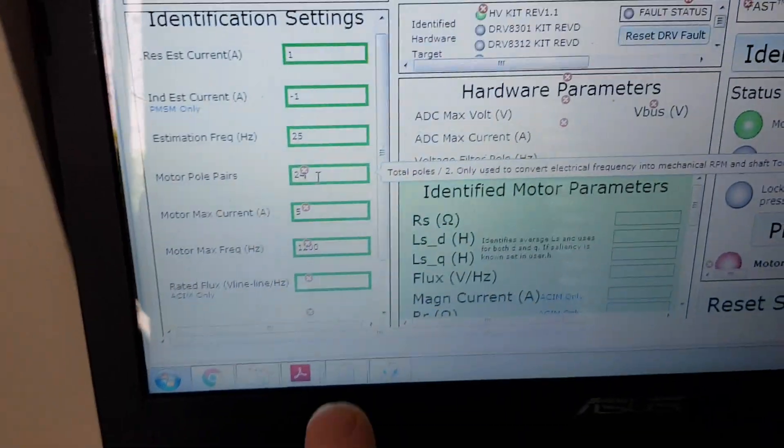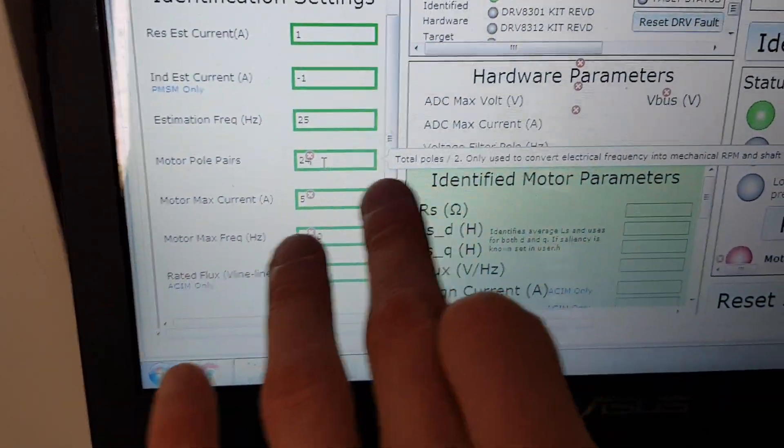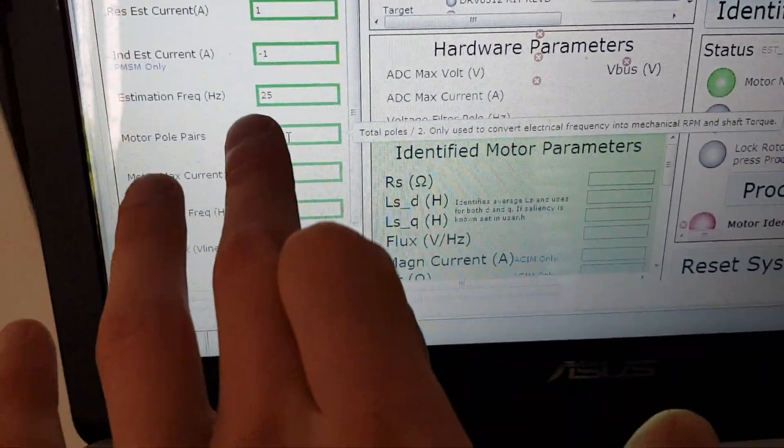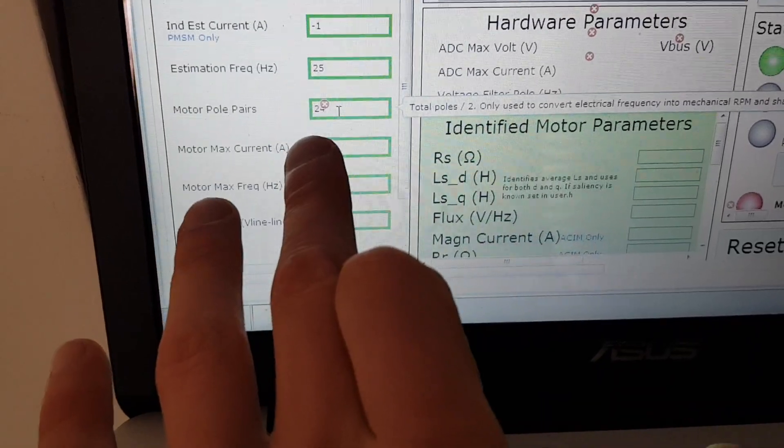These are the poles you see them. There's a lot of reflecting light but you understand what I'm saying. You have 48 magnet poles so here in the program they ask you to insert the number of poles but total poles divided by 2 so you're gonna use only 24.